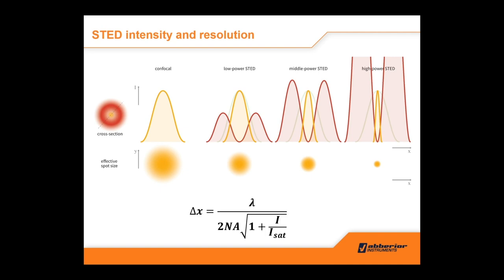This is the resolution formula: your resolution will be lambda — the wavelength of light — divided by two times the numerical aperture of the objective lens. There is an extra factor for I, which is the STED laser power, and I_sat, which is the saturation intensity of each fluorophore. It basically tells you how effectively the fluorophore is brought back to the ground state by the STED laser. If you increase I — the STED laser power — you will significantly improve your resolution.